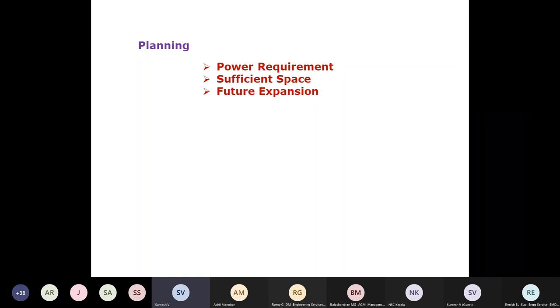So to avoid such difficulties in future, before starting the civil work, or at the time of starting the civil work itself, we should be aware of the power requirement of our installation and should provide sufficient space for installing transformers, panels and other electrical equipment. Also, we should expect future expansion. In every installation we will have to expand after a few years. Accordingly, new panels or new transformers or such equipment are to be installed. So considering all these things, sufficient space is to be provided at the initial stage of the project for electrical work.